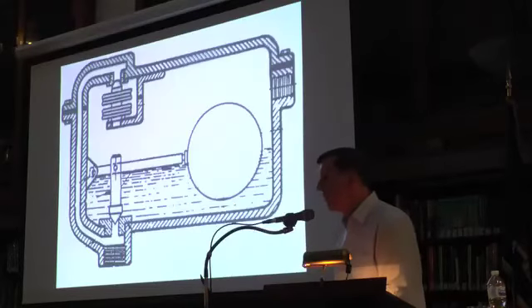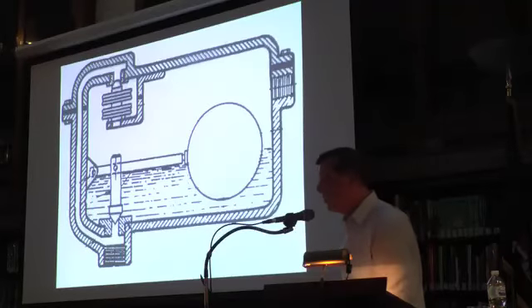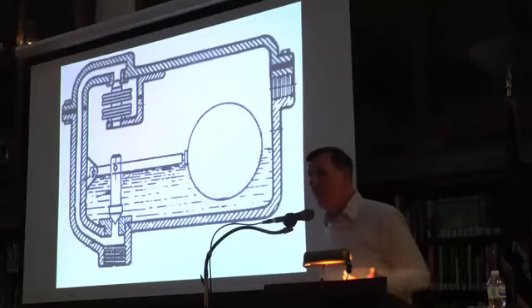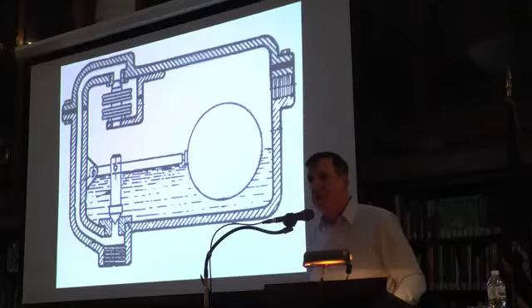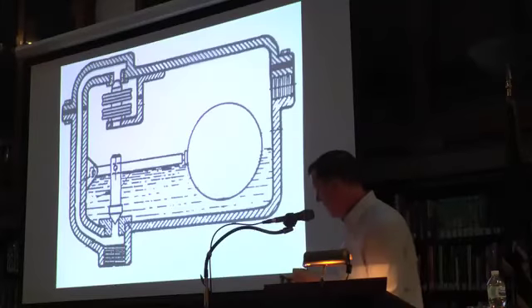But a float and thermostatic trap is quite different, because the thermostat here is there strictly to pass air. So the air comes into the trap ahead of the steam, goes there somewhere downstream. It's going to be vented from the system. And this is a normally closed trap. It's the weight of the float magnified by the length of the lever, and it pushes the pin into here. So when the steam comes in, it can't get out until it turns back into water. When it does, it causes the float to float up, and that pulls the pin out of the seat.